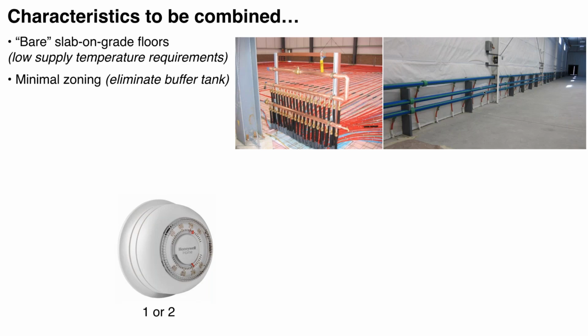Minimal zoning, and I say that because, again, we don't want to take a large slab, especially in a large open area, and just break it up into a lot of zones. There's really no gain in doing something like that. Now, we might have, I put down here below the thermostat, 1 or 2 zones. You may have a major shop area in a building and perhaps a smaller area that might be a break room, maybe offices, bathroom facilities, that type of thing. So I don't want to say just single zone, but minimal zoning where we aren't taking that mass and breaking it up into a lot of little independently controlled elements.